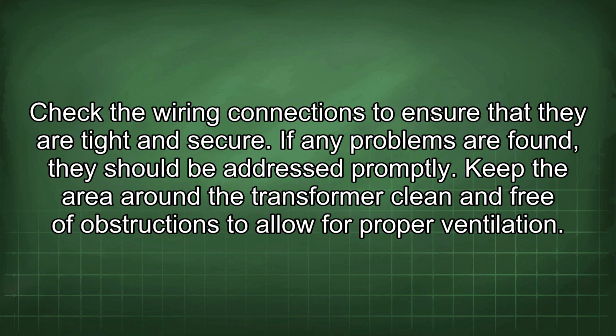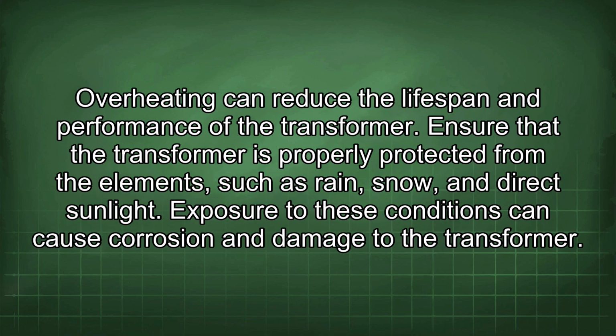Keep the area around the transformer clean and free of obstructions to allow for proper ventilation. Overheating can reduce the lifespan and performance of the transformer. Ensure that the transformer is properly protected from the elements such as rain, snow, and direct sunlight.